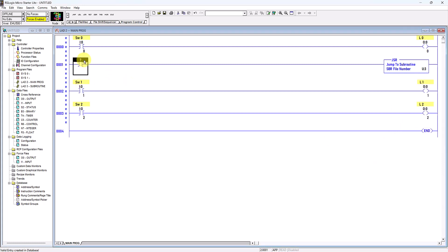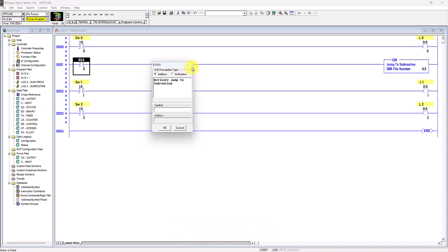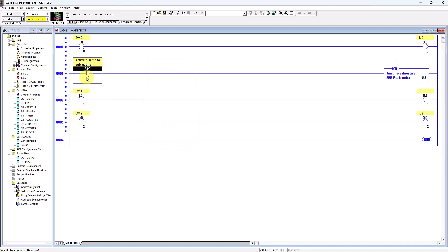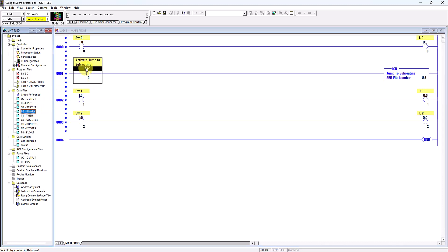For this contact I will use a Binary data file — B3:0/0. A word consists of 16 bits, from bit 0 to bit 15, and you can choose whichever bit you need. I will write the description as 'Activate Jump to Subroutine'. B3 means the file type is Binary and the file number is 3.